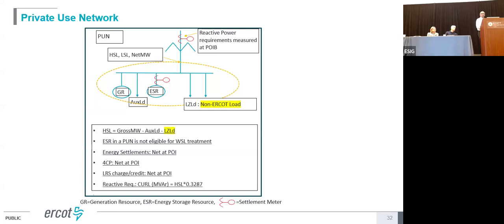The main reason why they may not want to register as a market resource is because they can only sell their surplus capacity into the market after serving their native co-located load. So in the example I gave, if the load is 400 megawatts and the backup gen is sized a little higher - say 500 megawatts - the maximum they can sell to the market is 100 megawatts of their capacity. This means they have to provide telemetry, provide their plans for the next 7 days, submit outages, and they might say that's too much of a headache. And there's compliance risk for 100 megawatts.